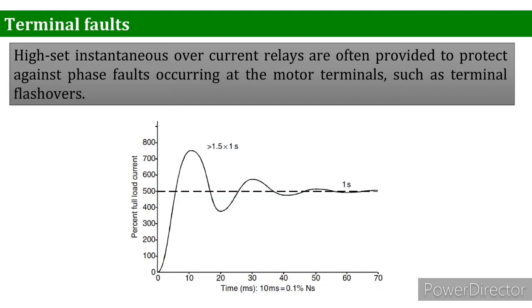you can see in the graph a typical motor starting current, a transient overcurrent during a few cycles when starting a motor. On the y-axis you can see the percent full load current, and on the x-axis you are seeing the time. You can see that in the first 10 milliseconds the percentage full load current increases up to 700.